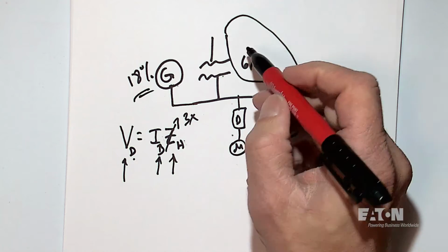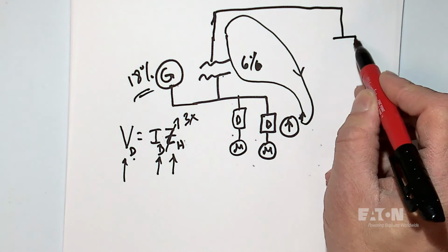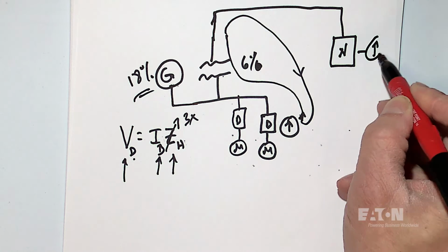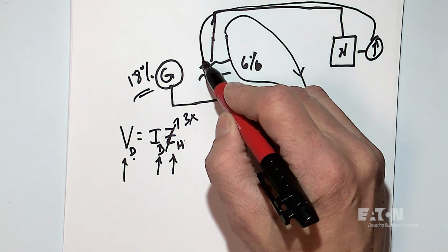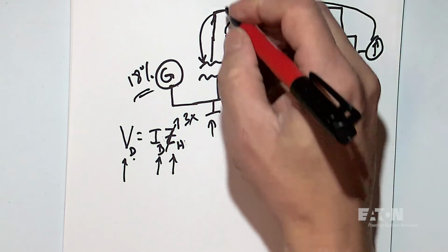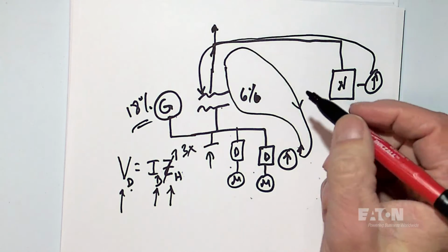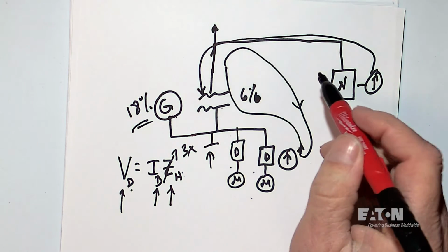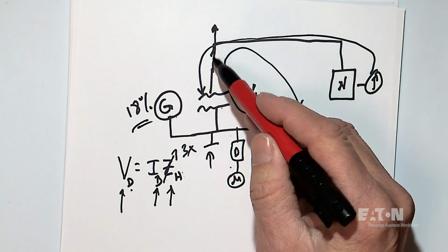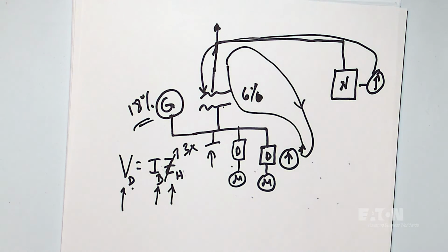So can the harmonics come from the utility? The answer is yes, only if I have another neighbor over here, Mr. Neighbor, who is producing this harmonic current. And if that current comes out, it might go over this way. The only reason it would want to come into here, though, to be honest with you, is if you have capacitors, because the source impedance looking this way is always going to look a lot better in terms of going back into the power system. So harmonic currents can come from the neighbor, but most of the time they're going to go back to the utility source. And harmonics can't really come from the utility unless they come in, again, for resonance reasons and other purposes.